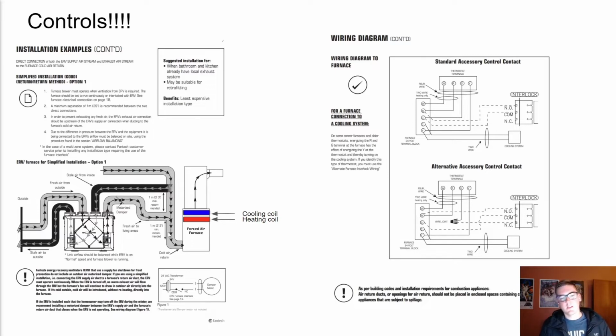So it could be discharged in here at 60 degrees, and all of a sudden you're recirculating that because your furnace isn't on, because they're not tied together quite yet. And then all of a sudden you get a chill in the room because you're actually cooling in the middle of winter. So that's not great.